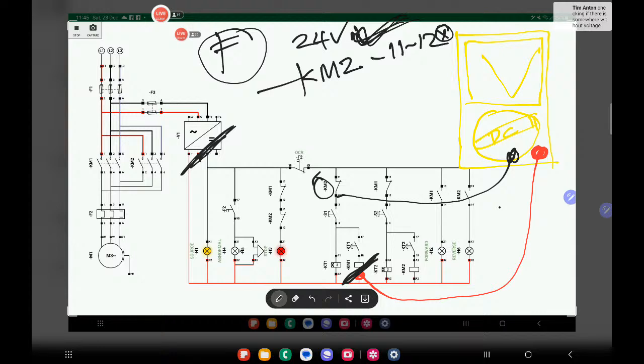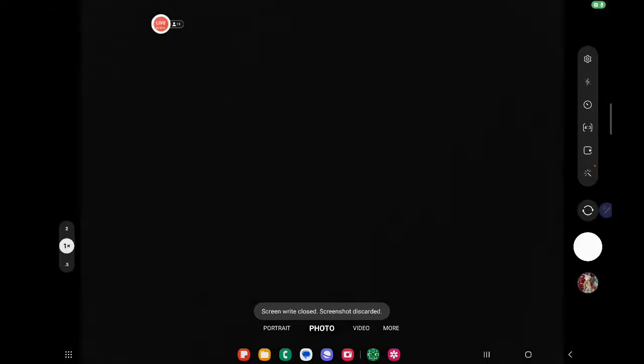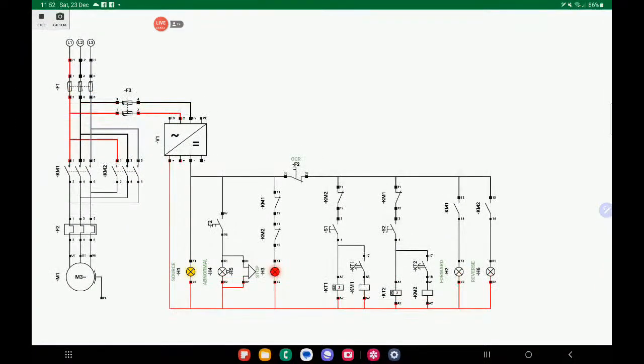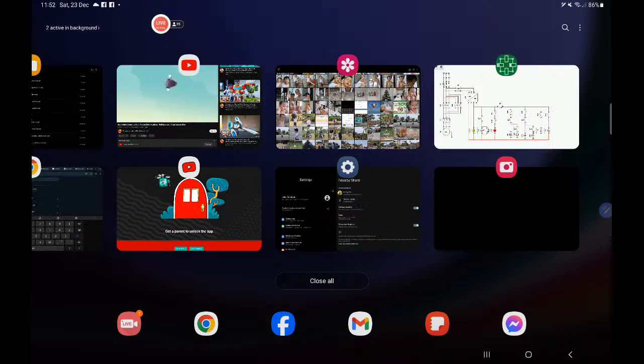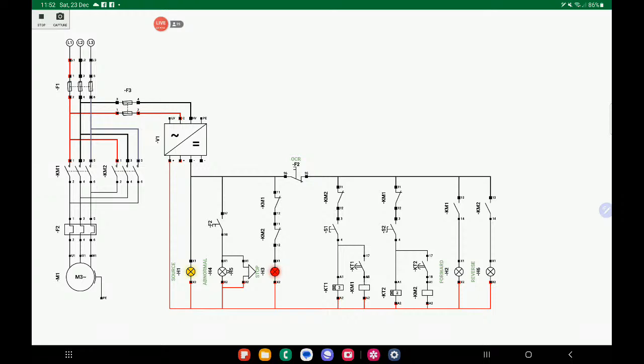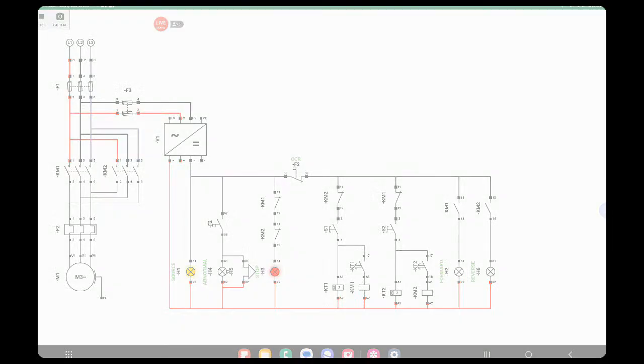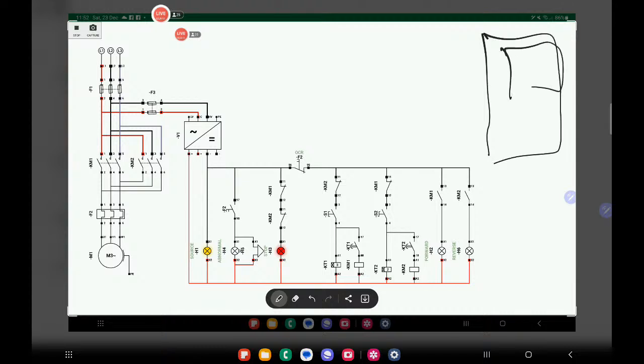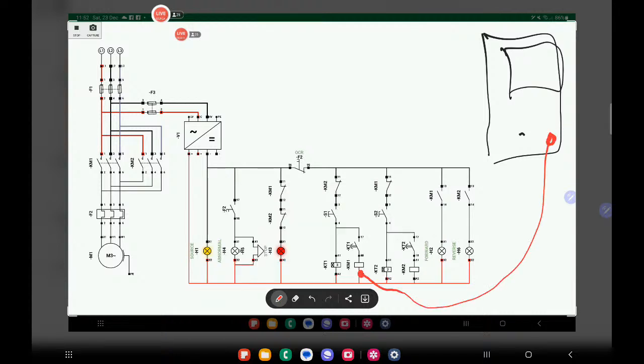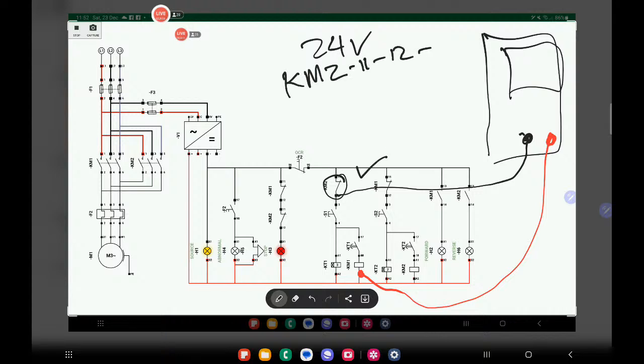But assuming that when I measure the KM2, I'm having also 24 volts, so KM2 would be okay. But I'll still put KM2 terminals 11 and 12 as the possible contacts for why you're not having a forward operation.